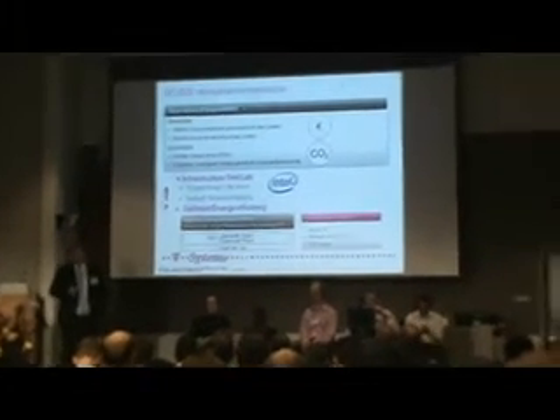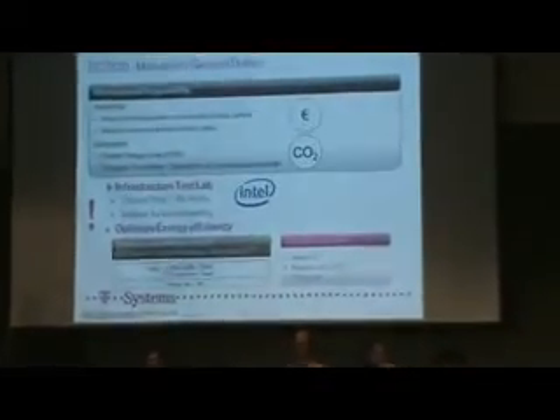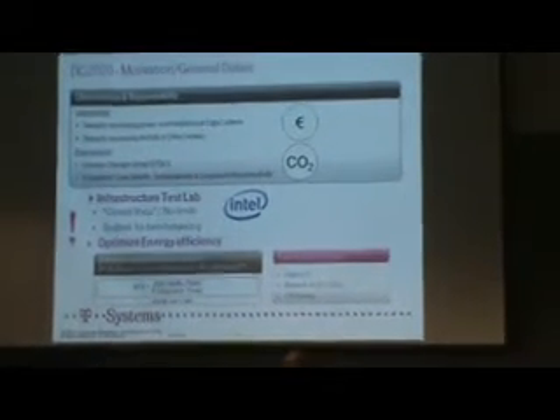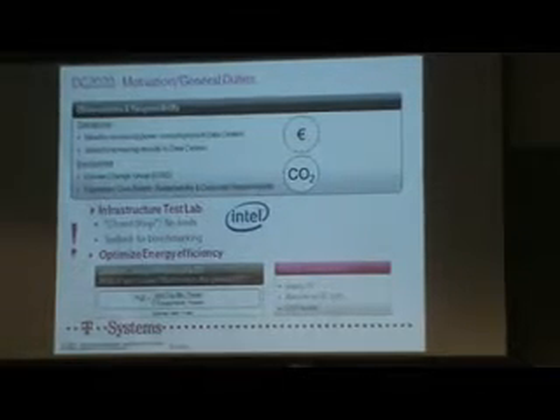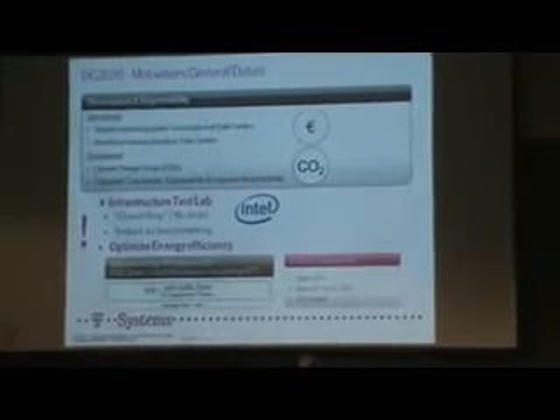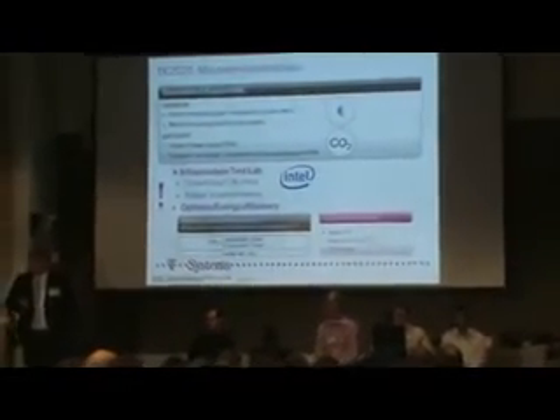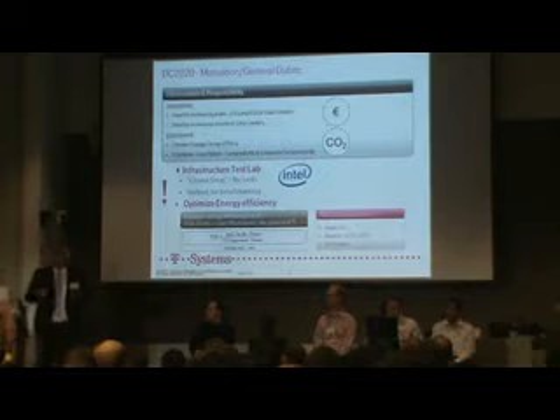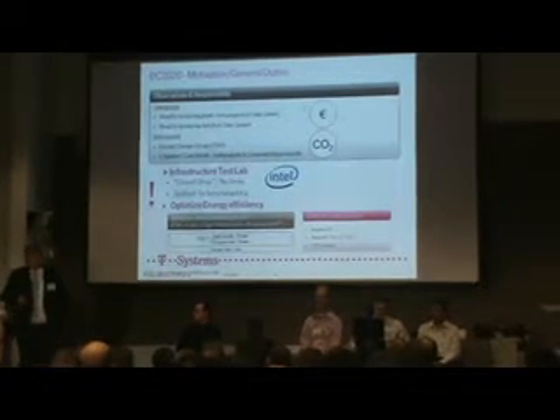It's a closed shop with no intersection to the production surroundings. We have no limits in this data center. In principle, you have the license to kill for the hardware you have in this test lab. And it's an ideal test bed for benchmarking and so on. The goal, as I mentioned before, is to optimize the energy efficiency, and for this we are using the PUE as defined by the Green Grid. It's the total facility power divided by the IT equipment power. And as a field for improvement, our legacy data centers are a blueprint for Data Center 2020, to build up in a greenfield approach in the near future. And we also use our results to optimize CFD models for airflows and temperature gradation in data centers.